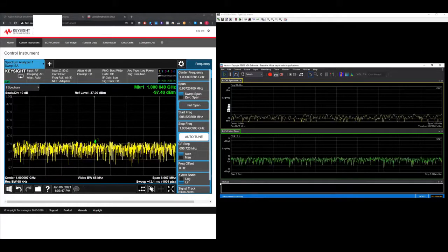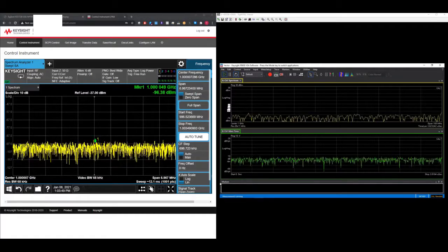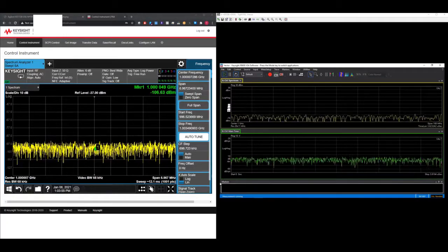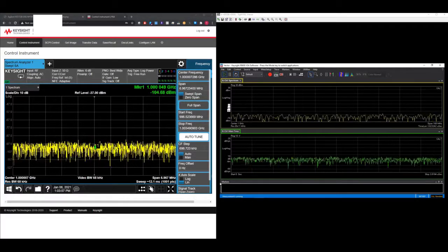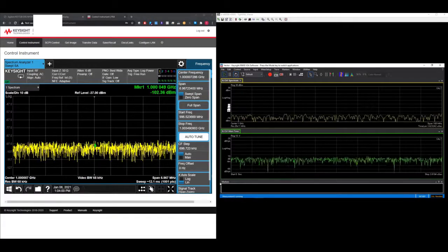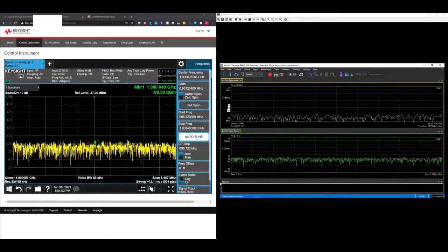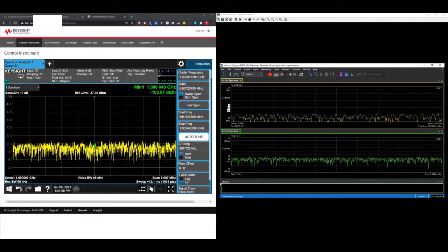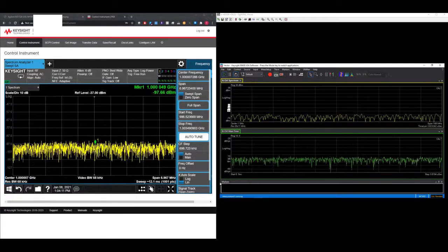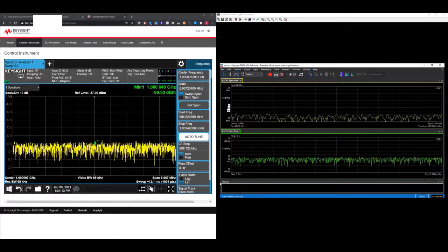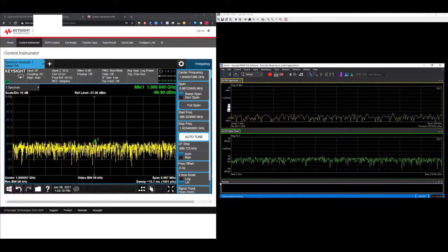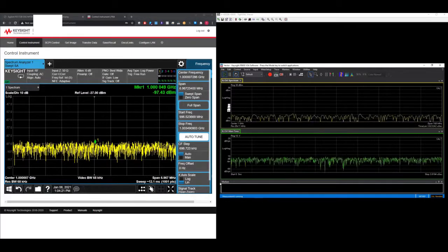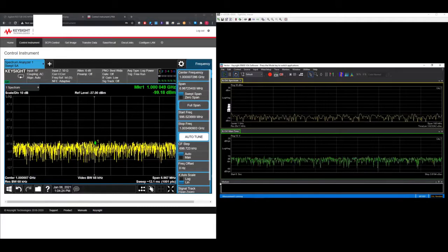First of all, we have to make sure that our PC is connected to a SIGGEN. For details on how to connect any Keysight instruments to your PC, you can check the other video within this channel. Just look for IP address setup. We have two options for that: one is DHCP and the other one is static. It depends on your situation, so just use whichever is suitable for your setup according to your IT profile.